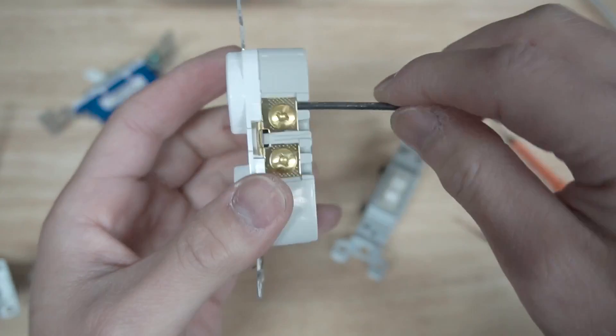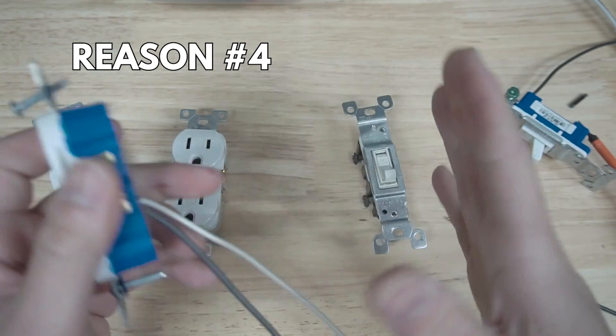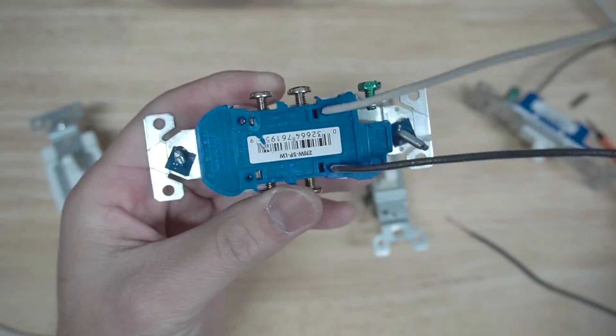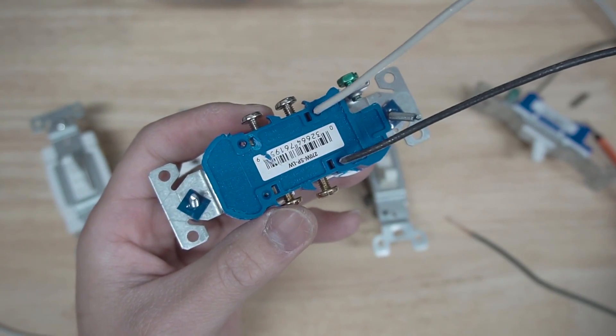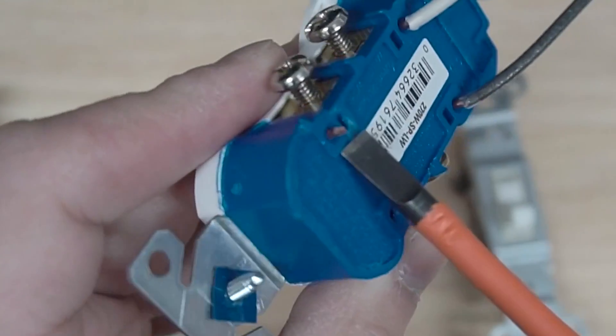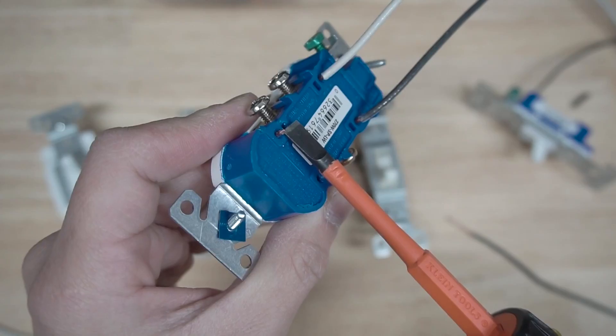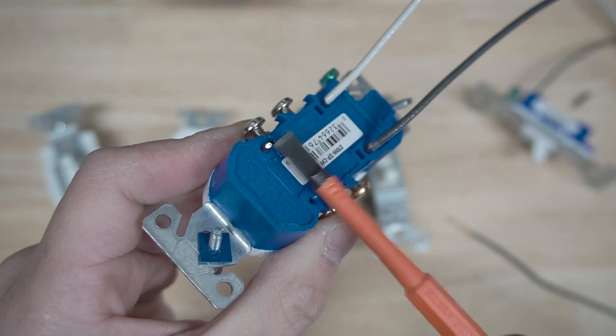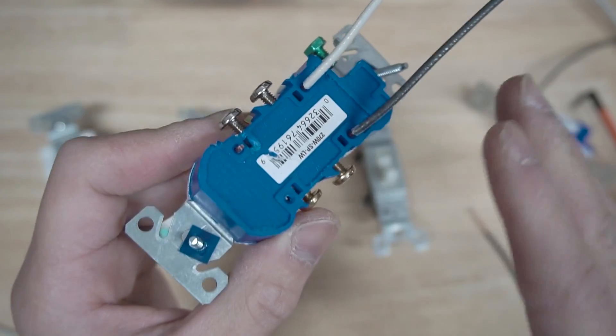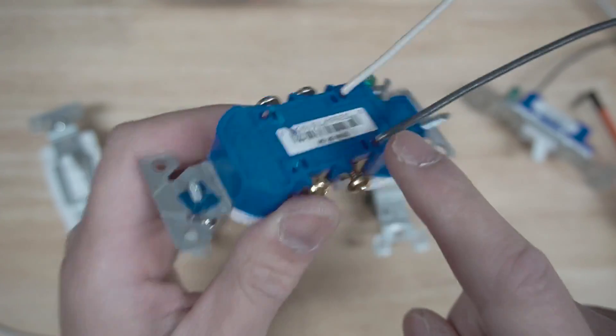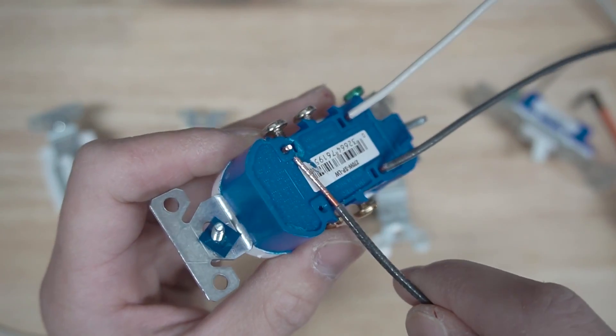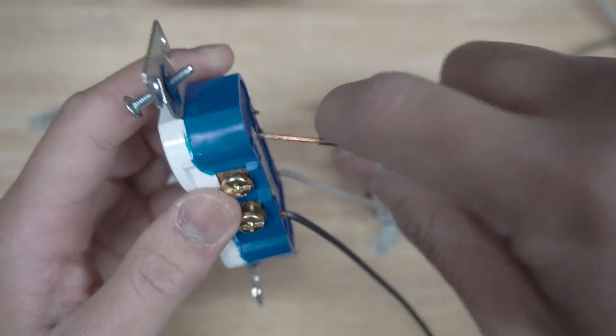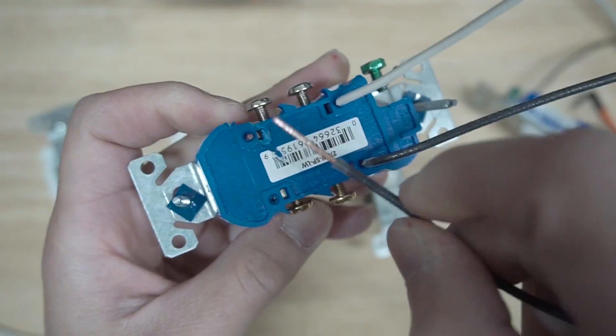Reason number four: now let's look at this receptacle. You see anything kind of weird about this receptacle? If you look right here, there's an actual wire that is sticking out. I've come to a few outlets or receptacles where I see this, and it becomes a problem. I actually went in a house and took out one of these things, and I saw one of these sticking out. The person who was installing it was probably trying to get that wire out really bad, and they didn't know that you can use those push-ins. They just ripped it, did the J-hook, and used the screw terminal.